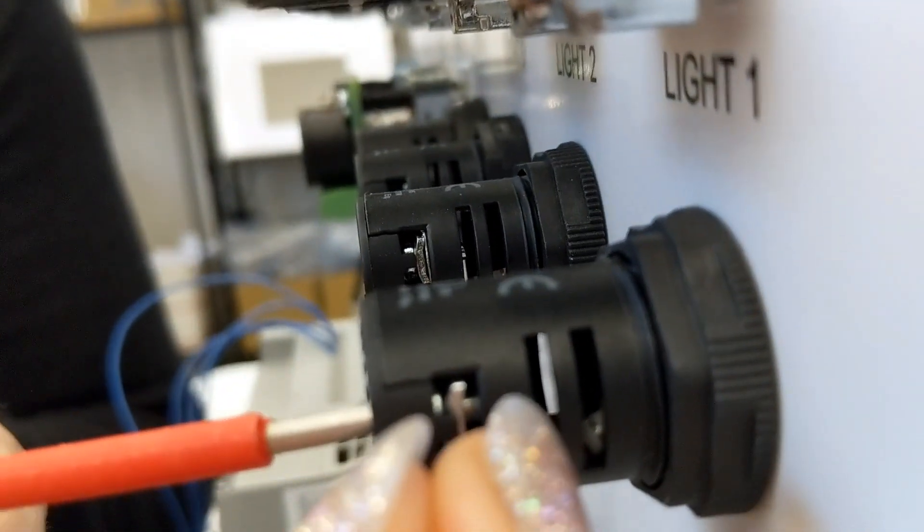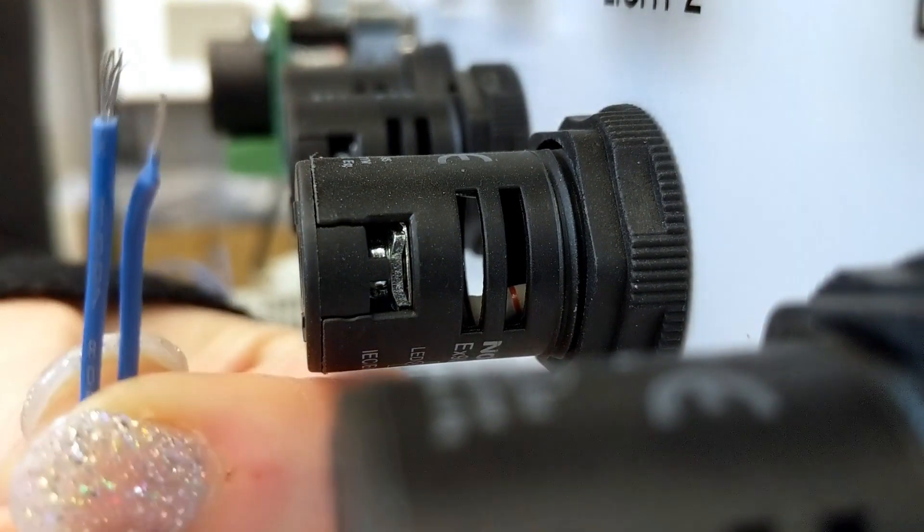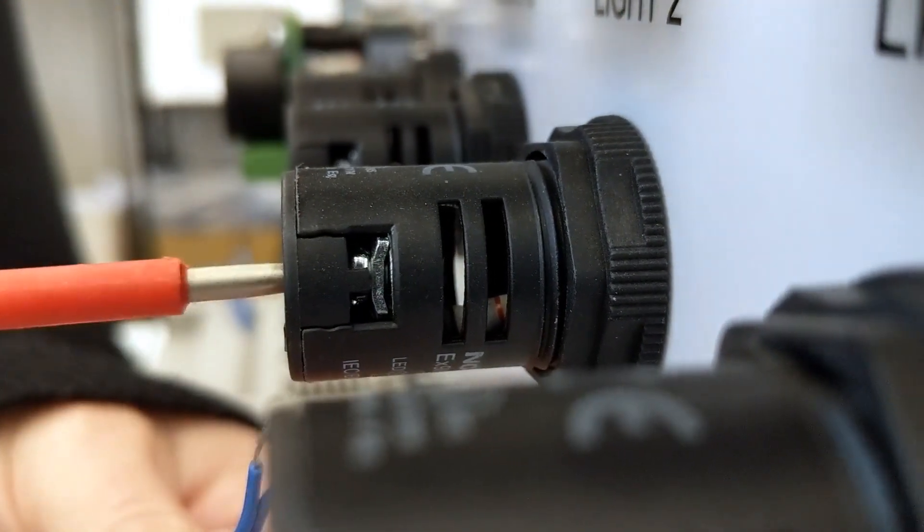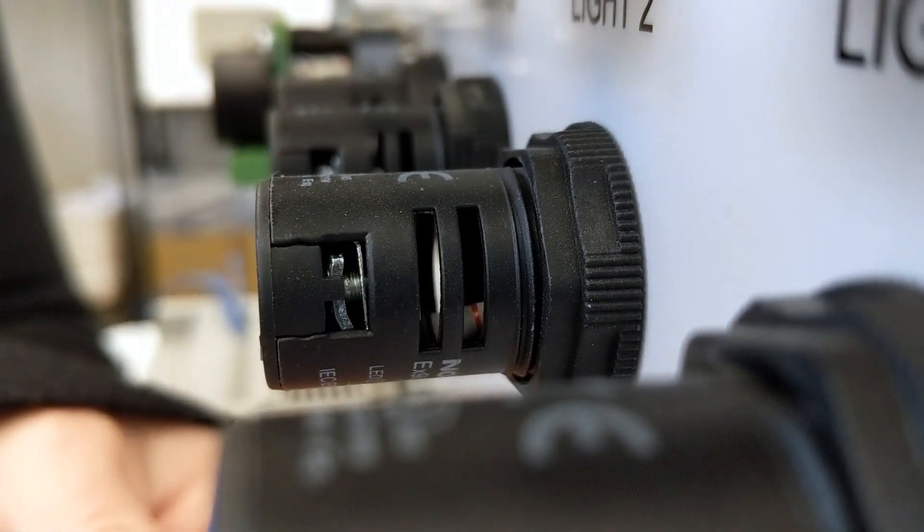Next, I'm going to connect the X2 common terminals to the lights. Just loop this from light to light, then loop it on the second set of gray terminal blocks to the left of the PLC, which is the minus 24 volt.